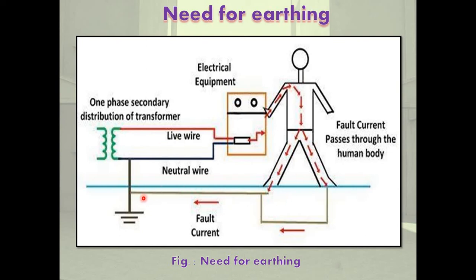The earthing system in electrical plants is designed such that the touch potential, the step potential, and the maximum current flow through the faulted structure and earth mat are less than the specified limit. Here are two important points: first is touch potential and second is step potential. Now, what is touch potential? The voltage between the feet on the ground and a raised finger touching a live part is called touch potential. The touch potential should be less than 30 volt RMS, like 42 volt peak. Now, what is step potential? The voltage between the two separated feet on the ground during flow of fault current through the underground earth mass is step potential. The step potential should be less than 30 volt RMS, like 42 volt peak.